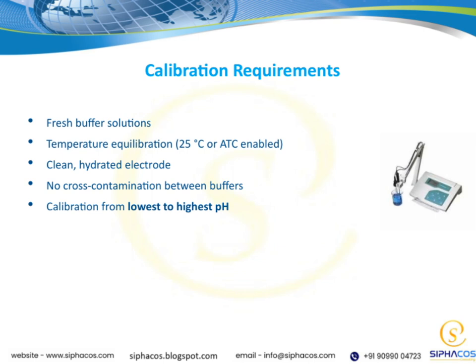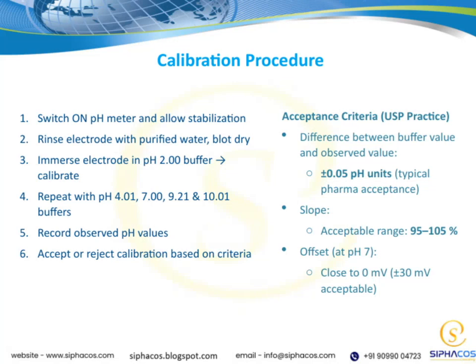Finally, when calibrating, always go from the lowest to the highest pH buffer. This standard practice helps maintain electrode consistency and accuracy across the pH range. Keeping these points in mind supports the overall goal of precise and reliable pH measurement in your work. Let's go through the acceptance criteria for USP practice.